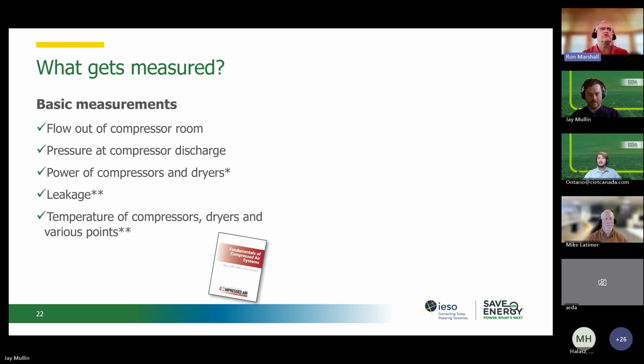And leakage, it's important to do some sort of leakage measurement. It could be done observing the main flow meter if you have a flow meter there, or doing point by point leakage, ultrasonic leakage detection effort, right? That could be done. And then temperature of the compressors, dryers, and various points. Temperature is so very important, and high temperature causes a lot of issues in terms of reliability of the compressor and the air quality, right? If the air going into the dryer is too hot, the dryer can't handle it and water goes into the system. And then water and oil start to cause contamination problems in the system.